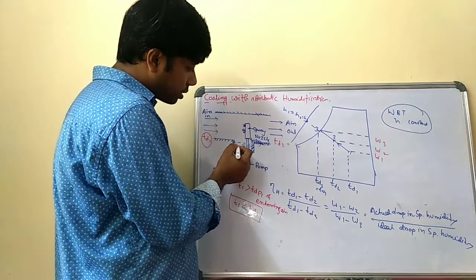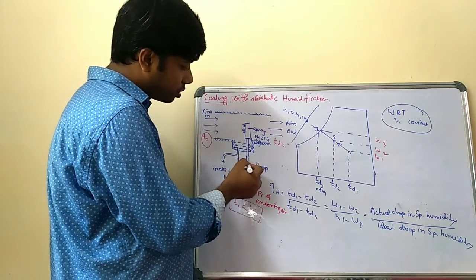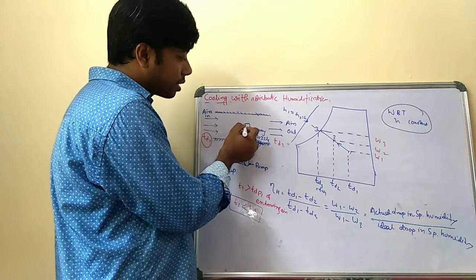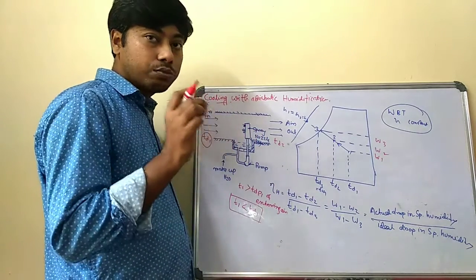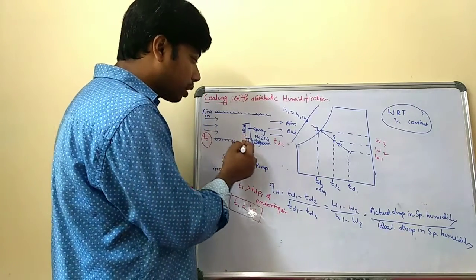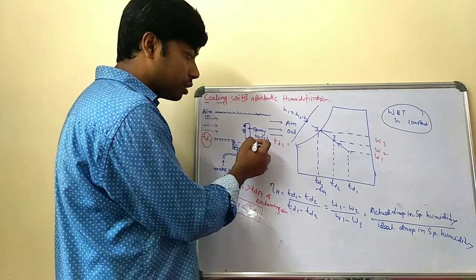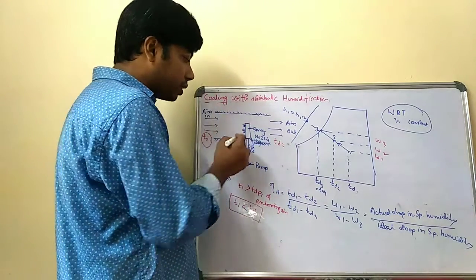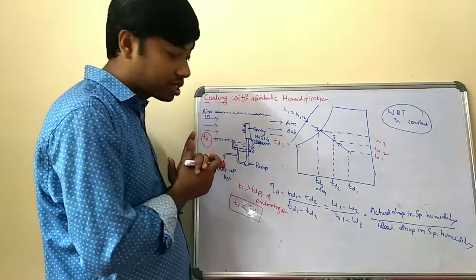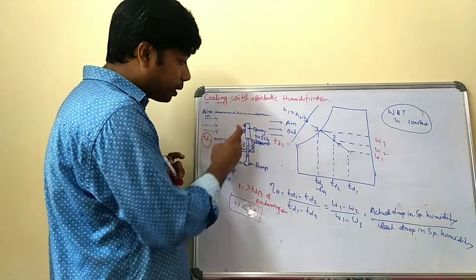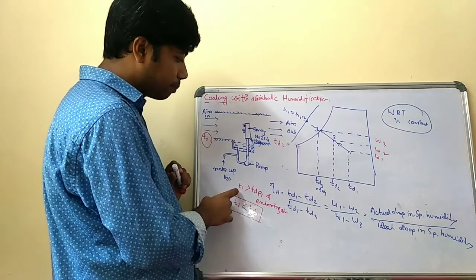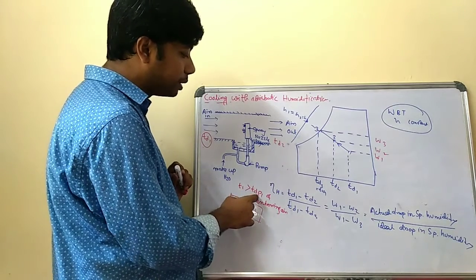In this chamber there is a water reserve. There are channels or pipes through which the water is pumped to the spray nozzle, so that it can spray small water droplets. The temperature of the liquid water stored here is T1, equal to TW1. For the cooling and humidification process, the condition is that the temperature of the spray water, T1, is greater than TDP1 of the entering air.